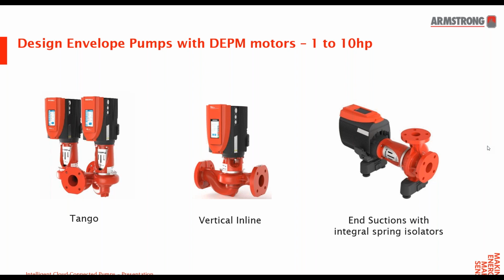As far as having pumps in parallel, it really depends on the designer, but obviously there'd be at least 2, and in some instances we see 3. In less common cases we've seen up to 4, and it really varies on how they stage them, so they aren't always running 2 at a time. We probably don't see more than 4 running at a time, because at that point the parallel pumping isn't adding a whole lot of additional pumping. It's just more redundancy. But 4 is the most we've seen operating in parallel, including North America as well as other parts of the world.